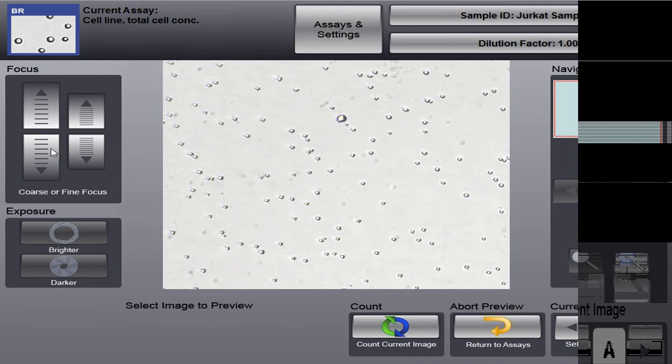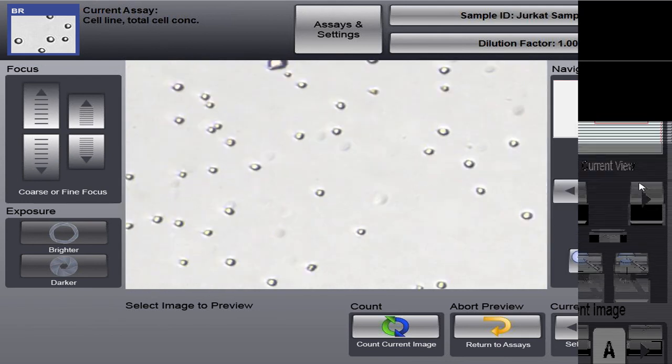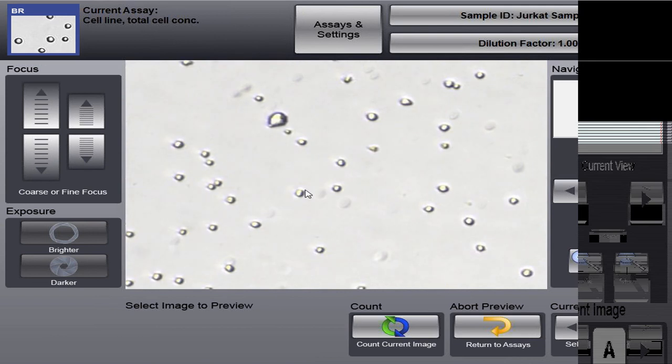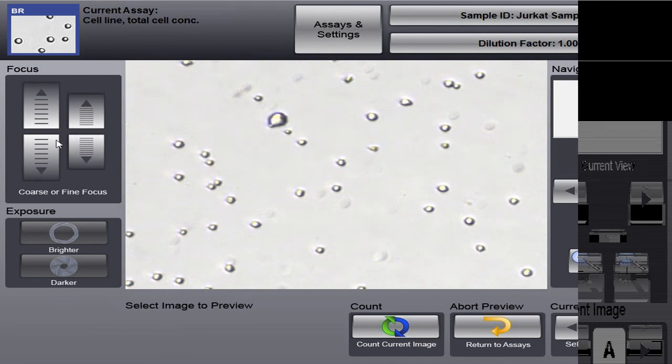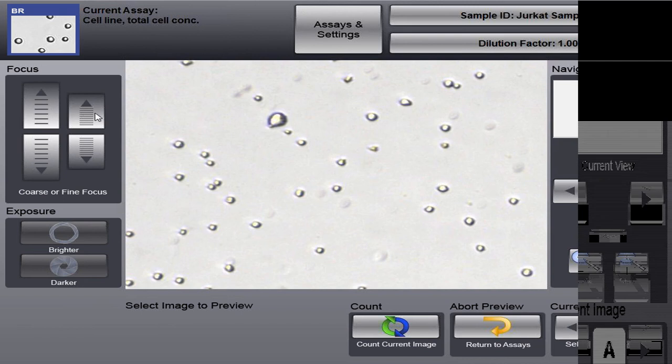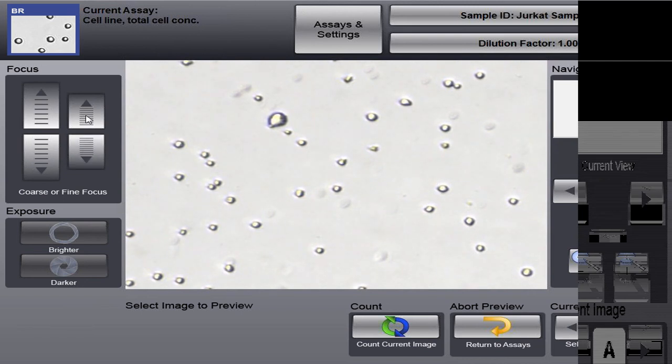Over here on the left, you see the cells are already in focus. Let me just zoom in so you can get a little better look at it. You see our cells are already in focus. We have a nice dark membrane, bright cell center. You do not need to focus in between samples. However, you may notice if you're counting a different cell type, there may be a slightly better focal position. And users can adjust that with these two focus buttons over here. So we have our coarse focus. If I click that, you can see that it makes a slight change. And then an even finer change is our fine focus. It's difficult to see, but it makes the fine tune adjustments to get that perfect focal position for your count.